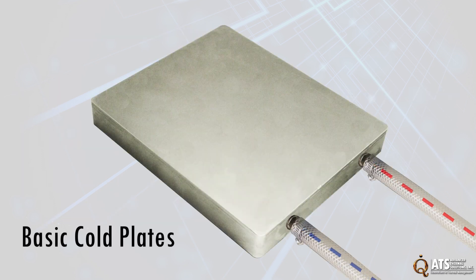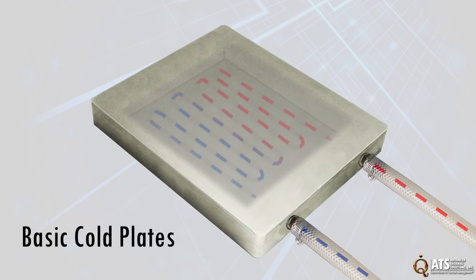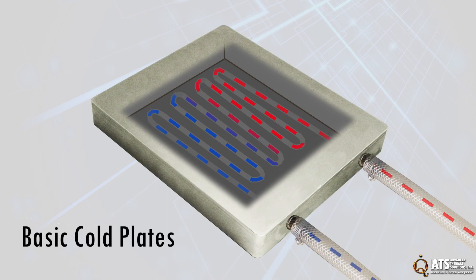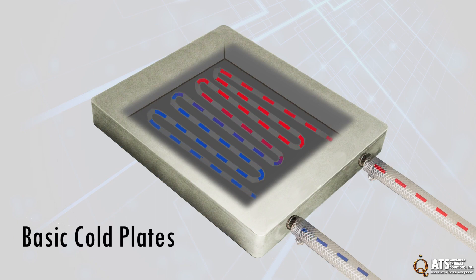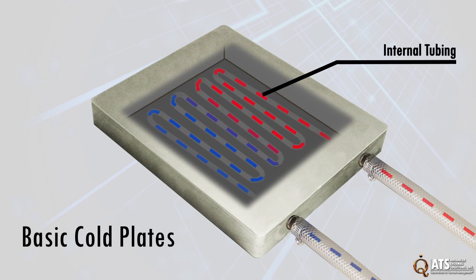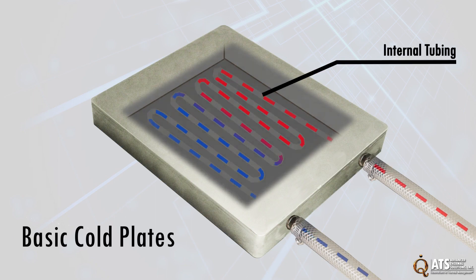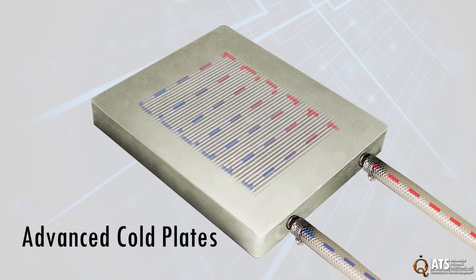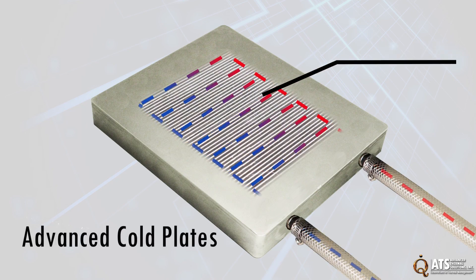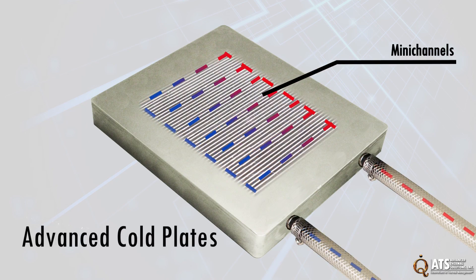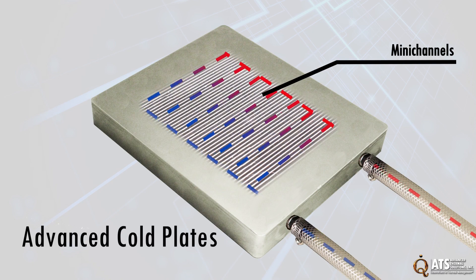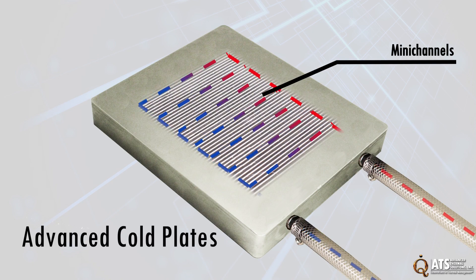At their most basic level, cold plates are metal blocks, generally aluminum or copper, that have inlets and outlets and internal tubing to allow liquid coolant to flow through. More advanced cold plates feature mini-channels to lower thermal resistance or use nanofluids as a coolant to improve heat transfer capabilities.